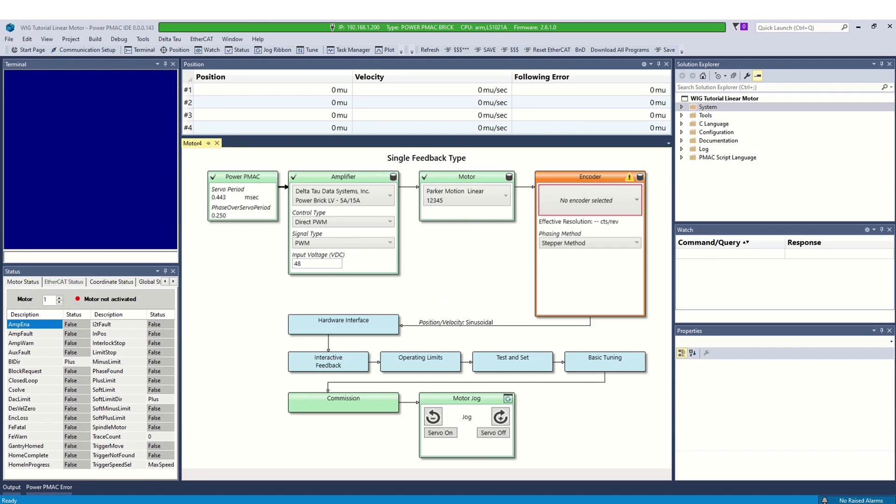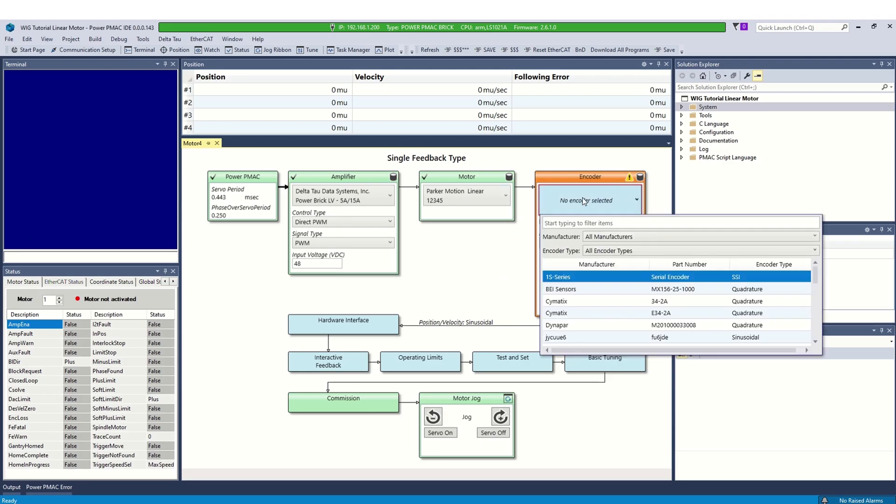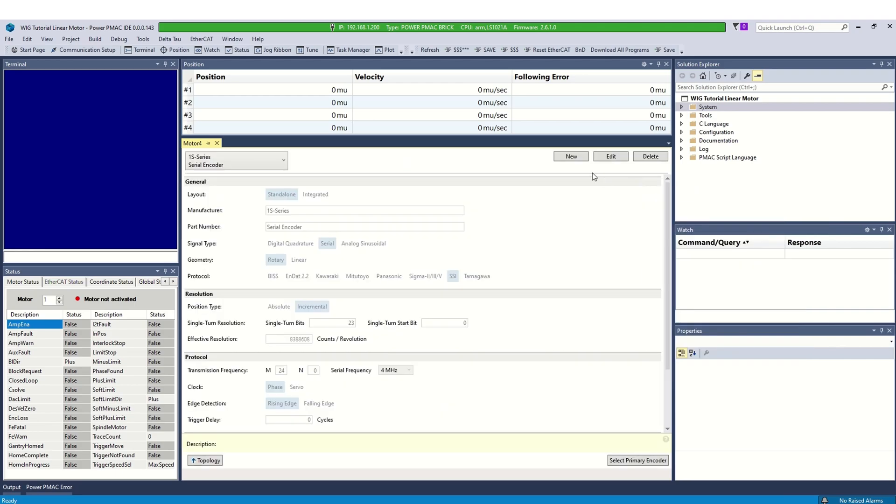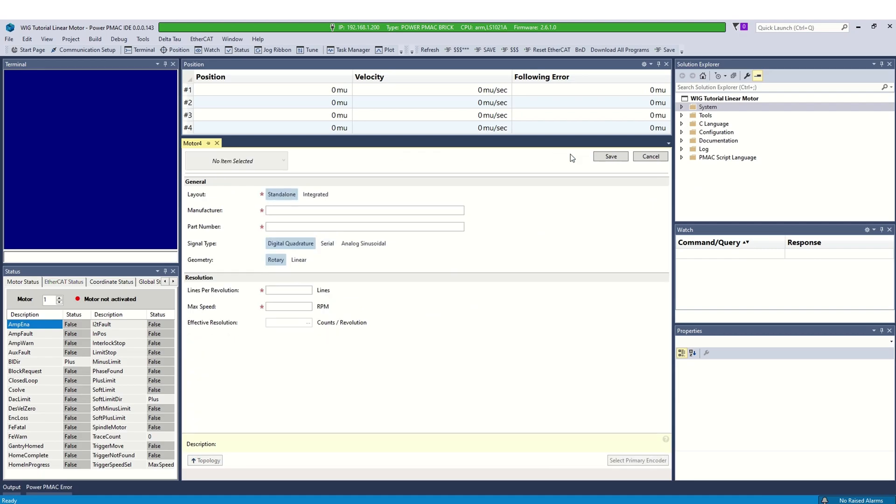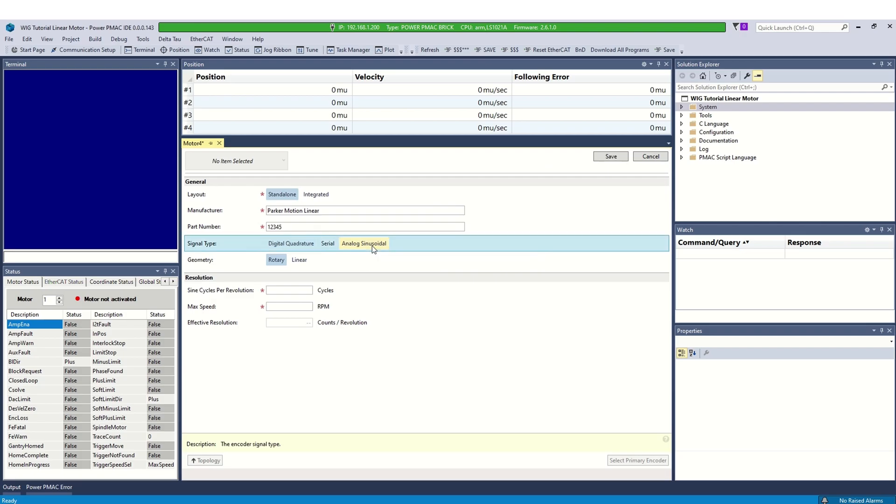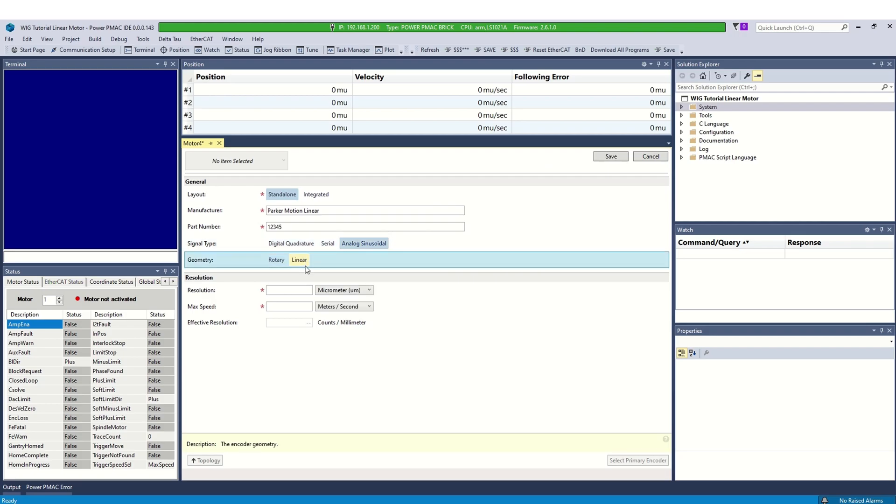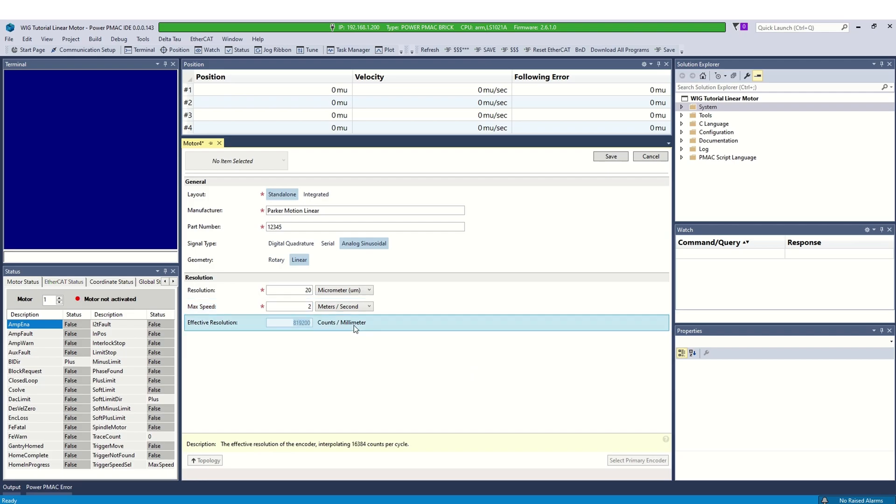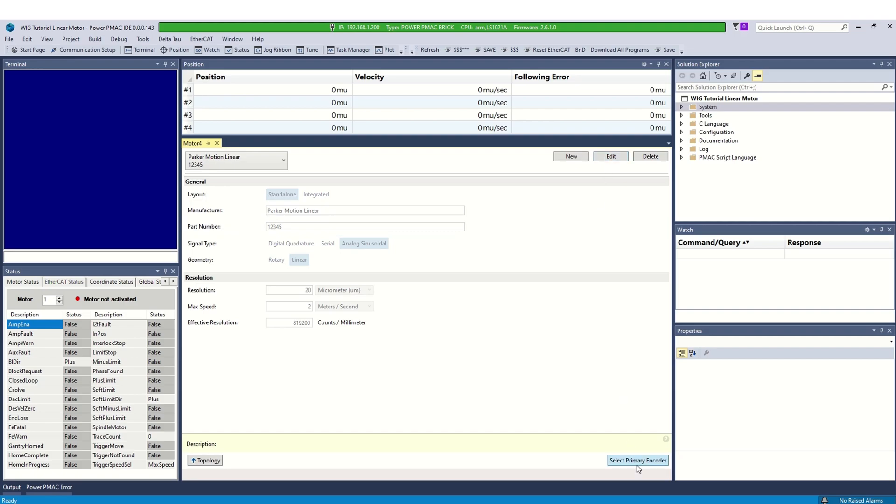Next step is encoder configuration. If the encoder is not listed in the database, open encoder details. Select add new encoder. Enter the manufacturer and part number. Select signal type as analog-sinusoidal and geometry as linear. Enter the resolution and max speed of encoder from datasheet. IDE will calculate the effective resolution. Select save to add encoder to database and click select primary encoder.